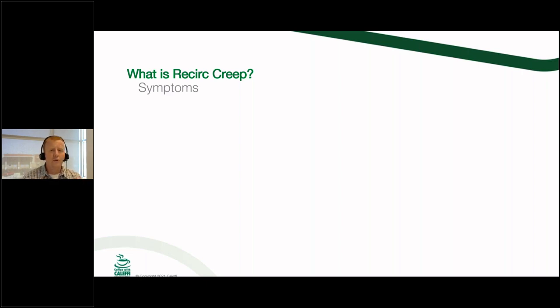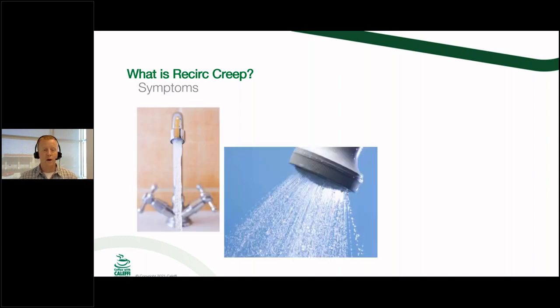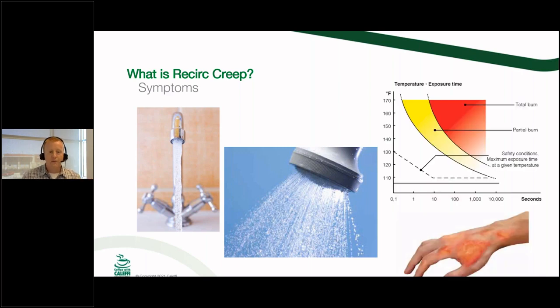And so what we want to do is go through the symptoms with recirc creep, because you may have already experienced it and you don't even really know how to kind of put your finger on it. It's something that you're not exactly sure what happened. Okay, so what you're typically going to find is you've got a domestic hot water system with a point of distribution mixing valve, and typically long periods with little to no demand from the domestic hot water system. And then you're going to have a recirculation system in there as well. And what you're going to find is whoever opens up that first faucet in the morning, because typically this long period of no demand is going to happen overnight, whether it be a nursing home or a healthcare facility, things like that, that first person is going to see some incredibly hot water, okay? Incredibly hot water to the point of scalding.